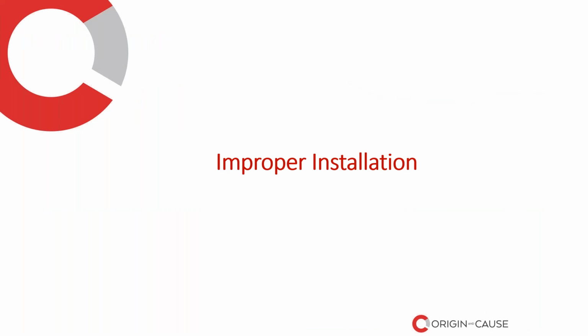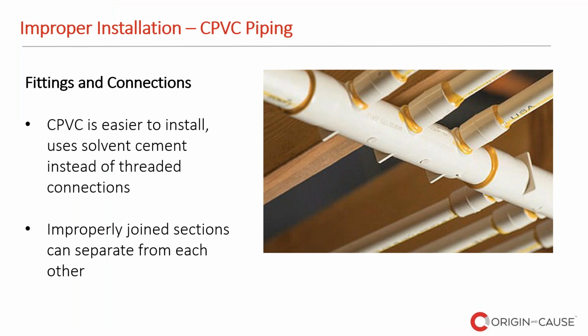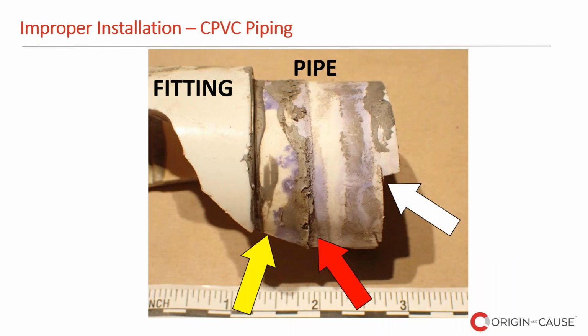When it comes to improper installation, in my experience, it's the second most common cause of failure. And when it comes to plastic pipe, the CPVC is obviously easier to install because it uses solvent cement instead of threaded connections, but improperly joined sections can separate from each other and cause significant damages. So I have a case study which I'm going to show, in which the joint was improperly made and it's separated.